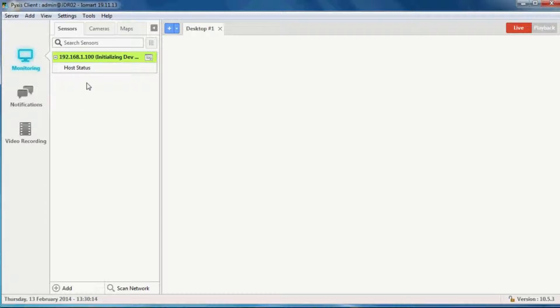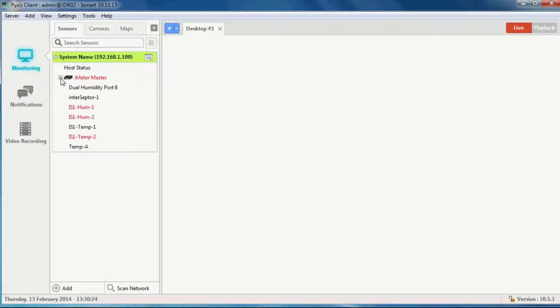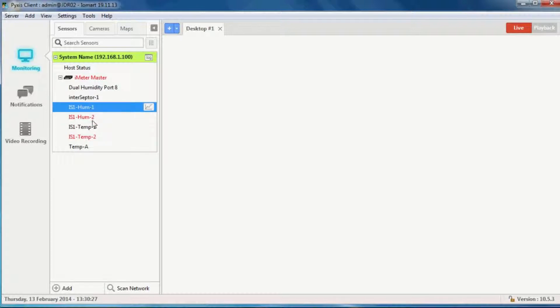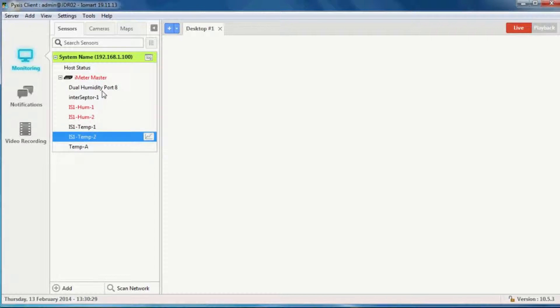Within the next few seconds I should get the list of sensors. It's come up as red because some of the sensors are in an alarm state. This information — thresholds, sensor names, everything — is taken from the iMeter, so you're not configuring in two separate places.